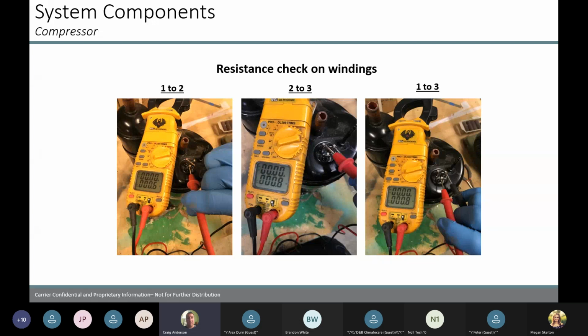If one's like 1.6 and the other one's 0.8, then we're looking for some issues. Plus or minus 5% is standard in the industry when we're checking resistance and stuff. So just make sure it's not well out of the equation when you're testing it. I suggest testing it from the plug that you pull out of the board. Then I suggest you check it right on the compressor too. This is going to eliminate any problem that might have occurred within that wire.